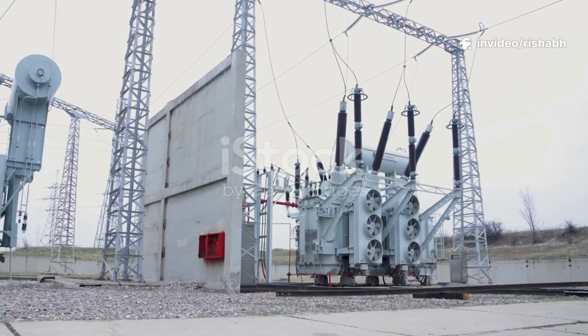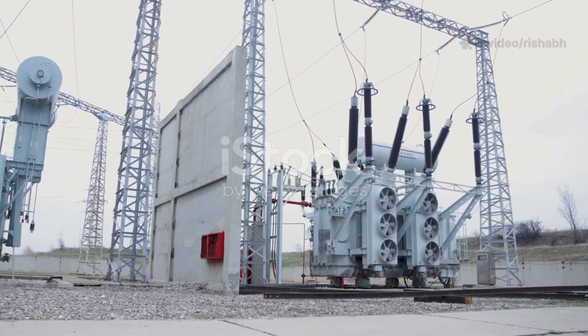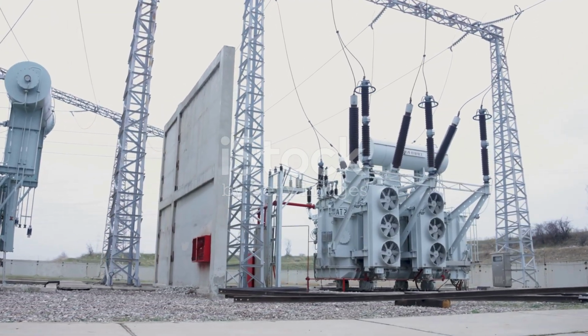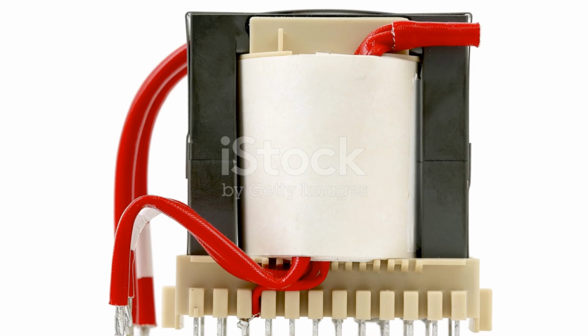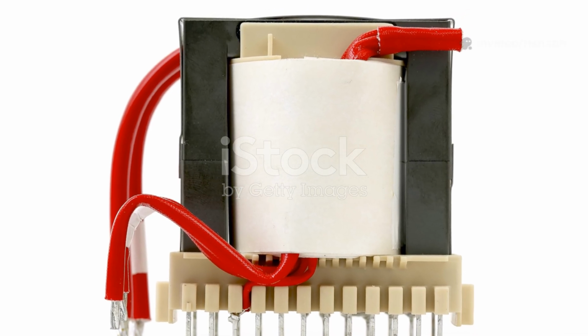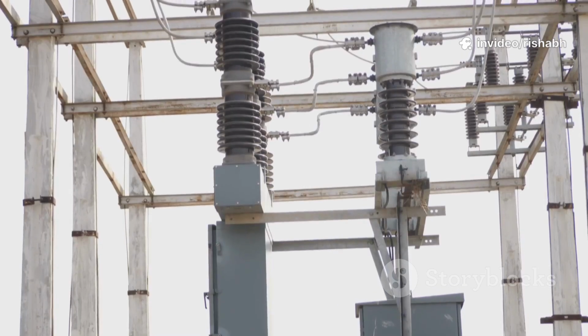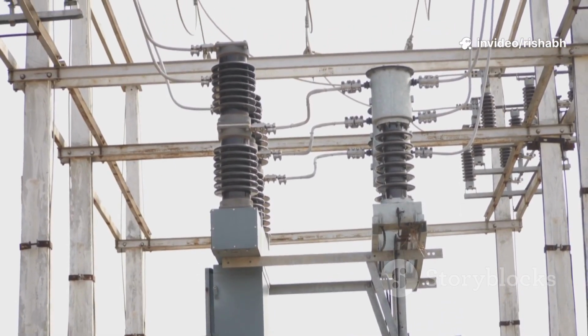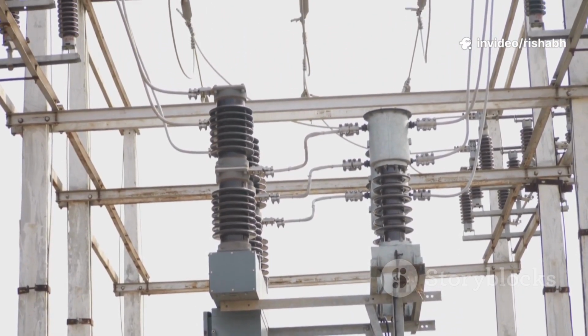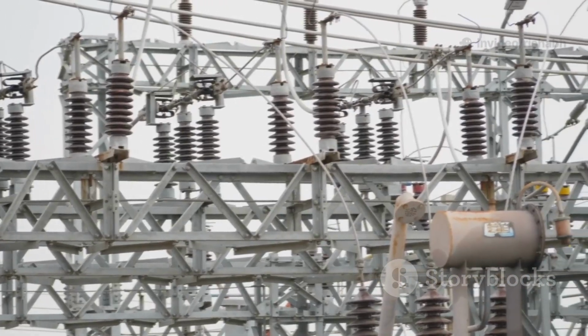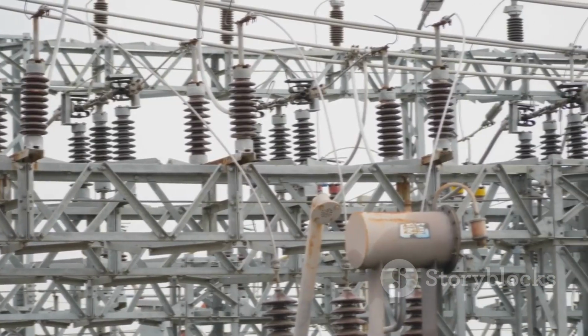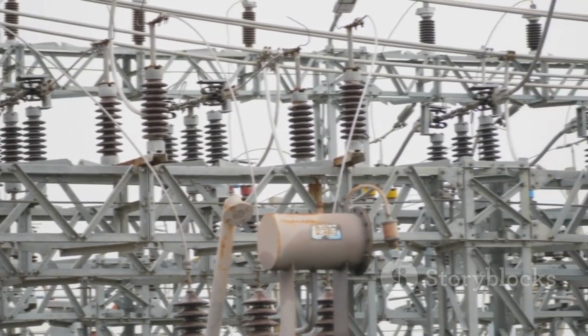A power transformer is, well, a world of extreme electrical stress. Hundreds of thousands of volts separate the windings from each other and from the grounded tank. Preventing a catastrophic flashover requires a robust insulation system. This system is actually a partnership between solid materials and a liquid dielectric.